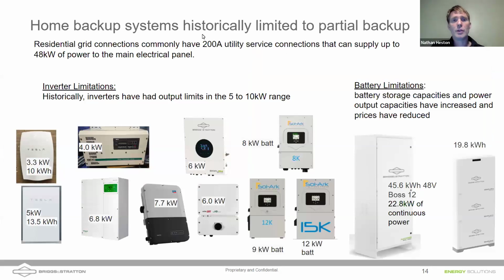Home backup systems have historically been limited to partial backup, and this really has to do with the fact that most residential connections are 100 to 200 amp or larger services, and that main loads panel of the house is capable of supporting 48 kilowatts of power, right? Most inverters have been much smaller than that. The Tesla Powerwall 1 came out at 3.3 kilowatts. Older inverters, a Trace inverter there, showing at 4 kilowatts. The Powerwall 2 went up to 5 kilowatts. Got the Schneider XW Pros there, Sunny Boys, SolarEdge inverters.